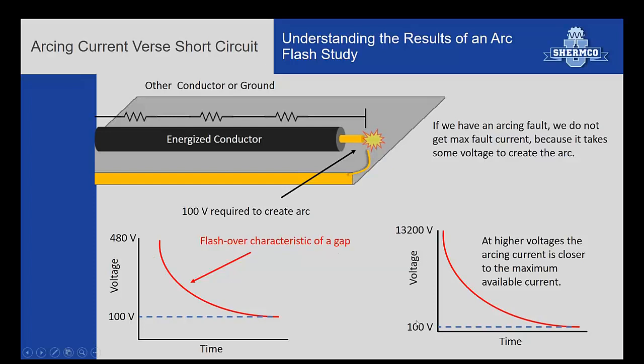The same type of arc on medium voltage gear, if it takes about 100, it'd probably take a little more because your spacing would be a little more. But you'll see that arcing current on lower voltages is much different than short circuit. Arcing current versus short circuit current on higher voltages is very similar. So it's a big difference depending on the voltage. But what studies are based on is arcing current.